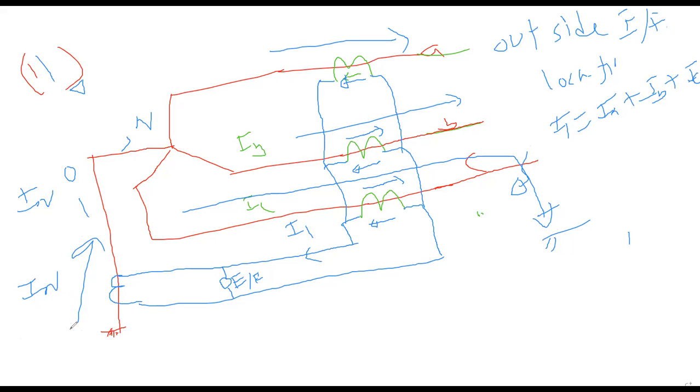As the neutral current is flowing in the upward direction, the secondary current will be in the downward direction, right? In this way. Yes, sir. So these two currents are now entering the relay coil opposite to each other, right? One is entering in this way, another in this way, isn't it? Yes, sir. And this neutral current, IN, is also the summation of the three-phase currents, IA plus IB plus IC. Can we say that?